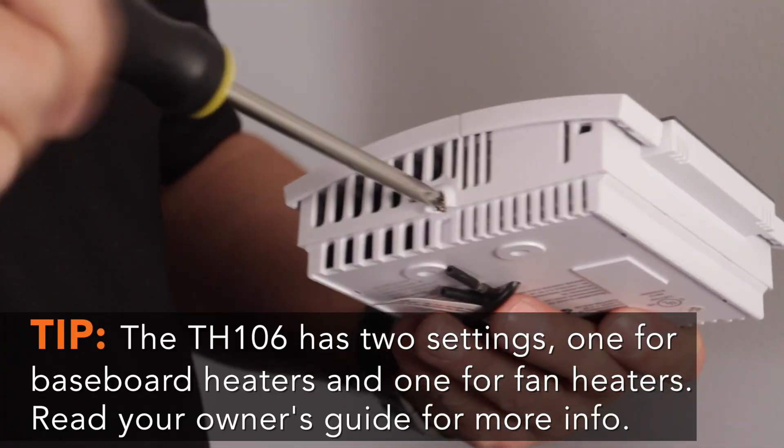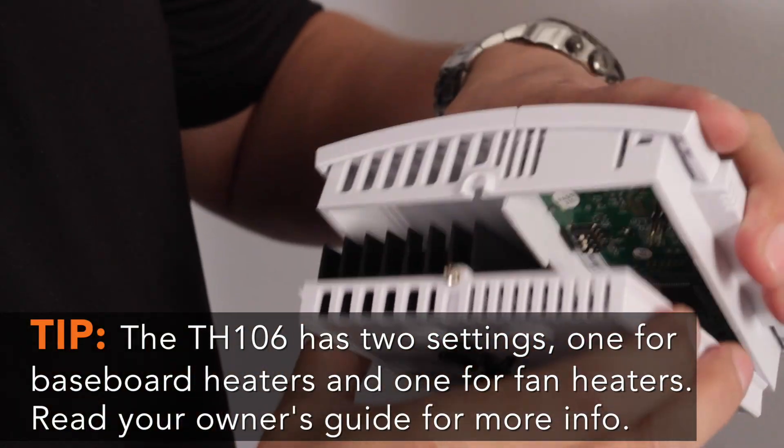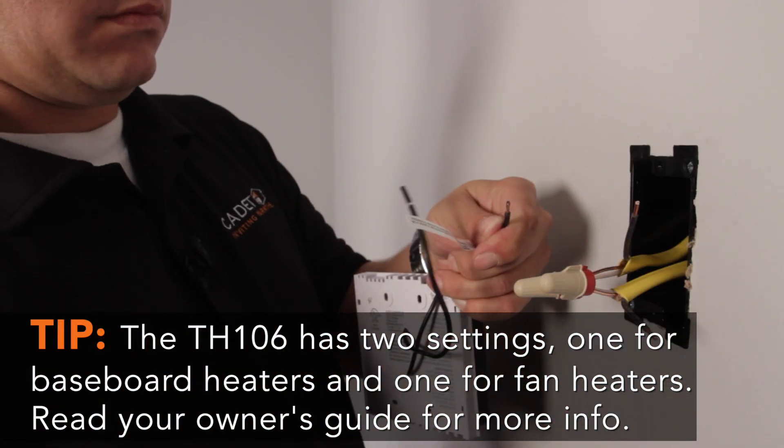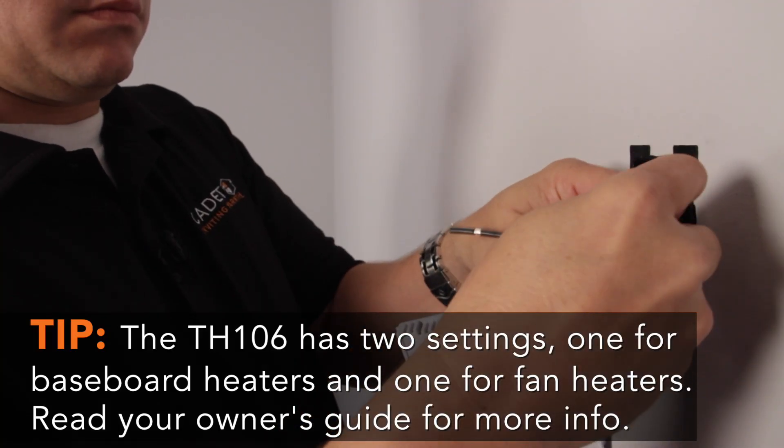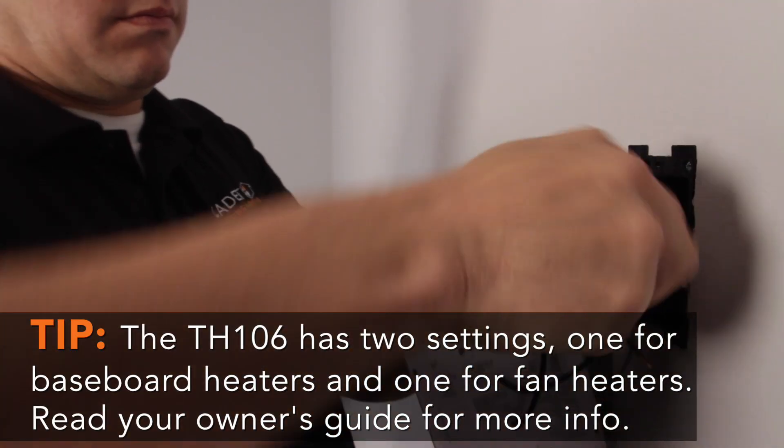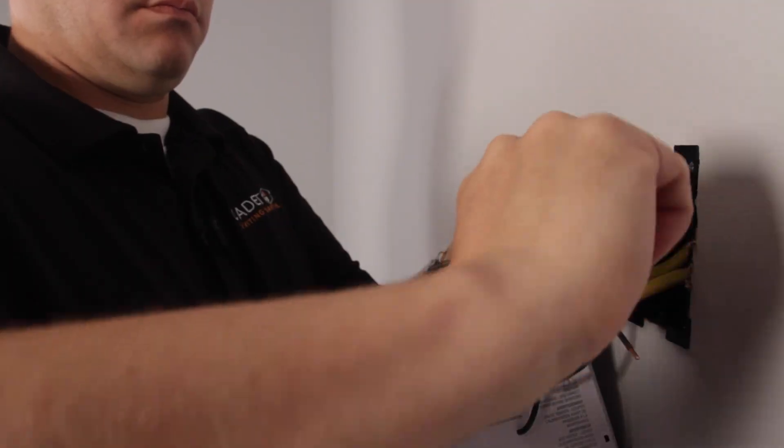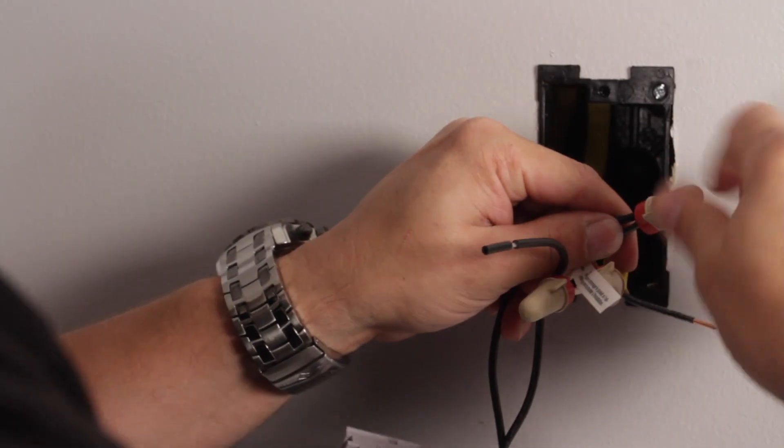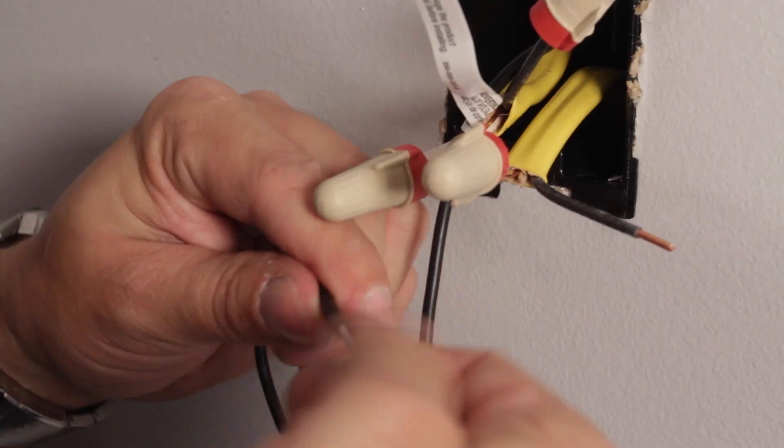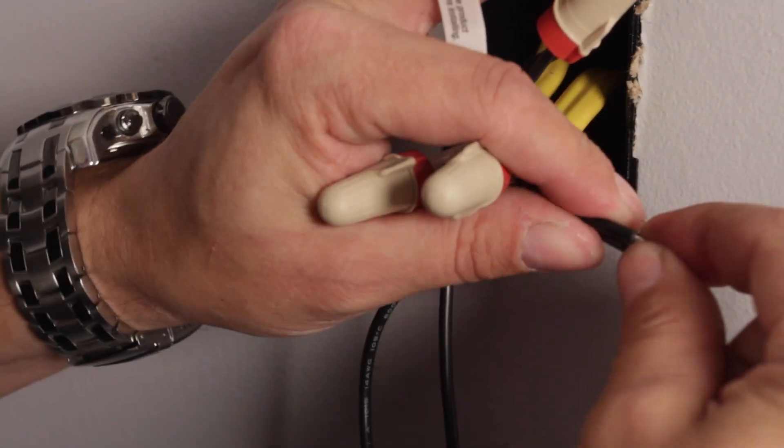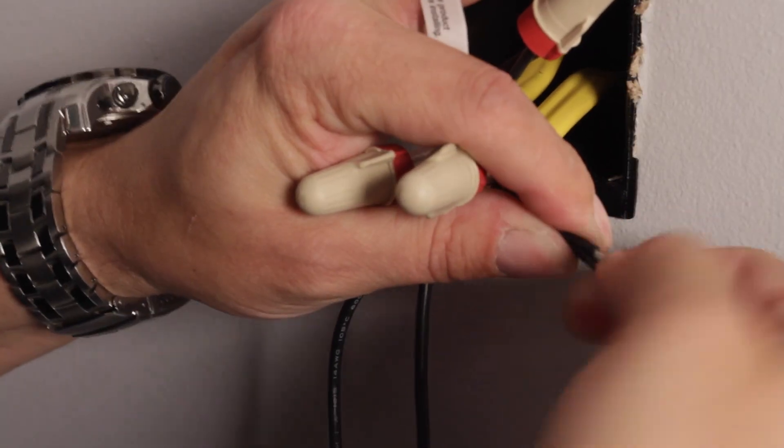Unscrew the set screw and disconnect the thermostat from the sub base. The TH106 is not polarity sensitive, so you can connect either black wire on the sub base first. Connect one wire from the sub base to one black wire coming from the J-Box. Now connect the remaining wire on the sub base to the remaining black wire in the J-Box.